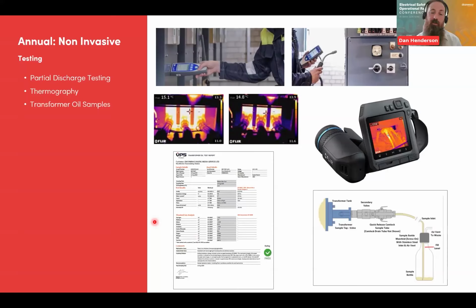We've got thermography, which is obviously recommended in NFPA 70B, where we can pick up temperature differential, we can pick up hotspots, things like that. And finally, transformer oil samples. So making sure you're doing your oil samples, but making sure you're interpreting the results and you're doing them to a standard that you're actually going to get some benefit from.